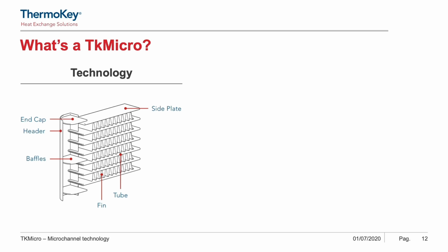It is an assembly made by 3 main parts. A set of multi-port extruded tubes are inserted within 2 lateral manifolds. Fins are created by folding aluminum strips and put in between 2 adjacent tubes. Input and output connections are brazed on manifold surface. Baffles can be hosted within manifolds, and they are used for governing refrigerant flow within the microchannel core.